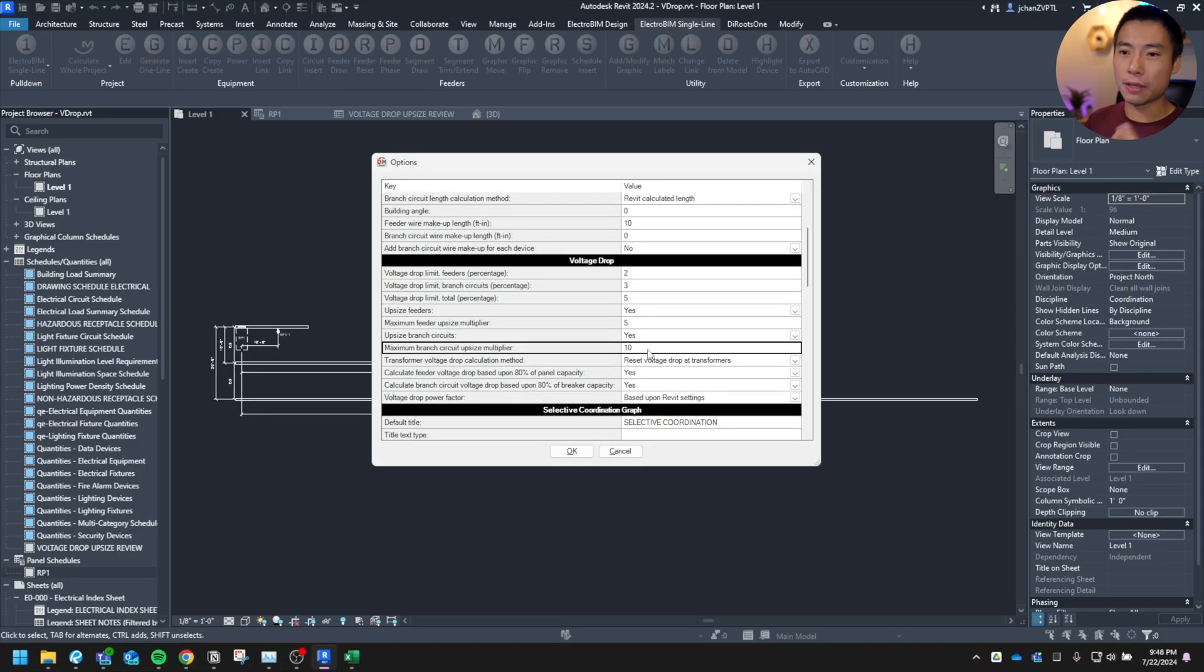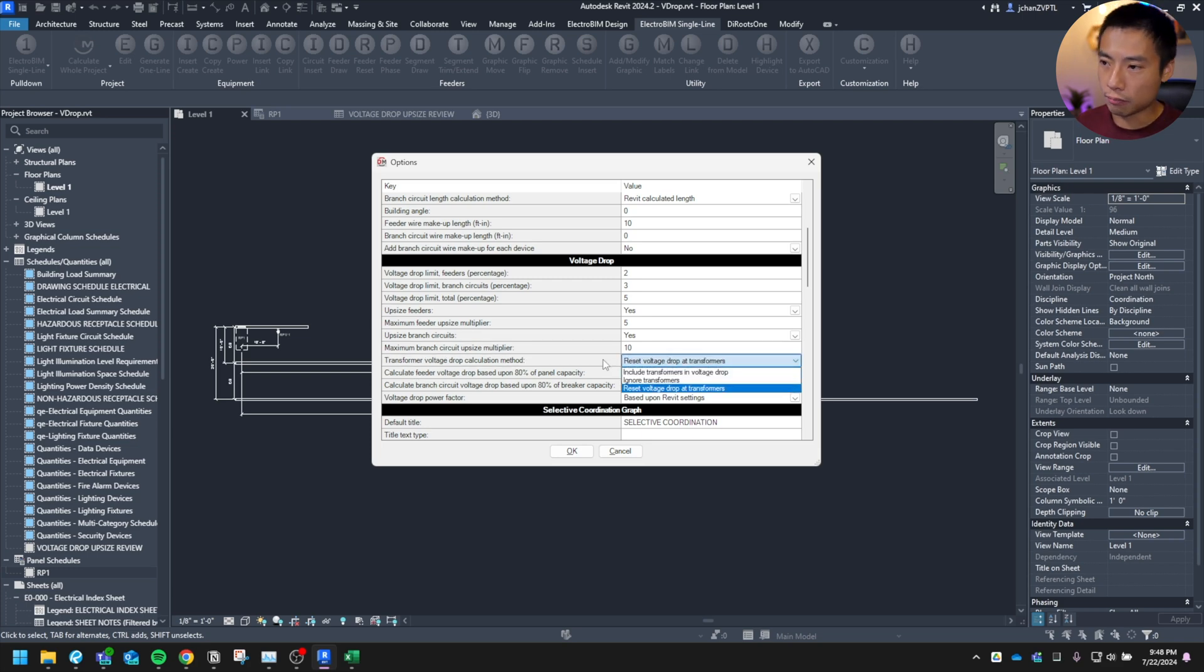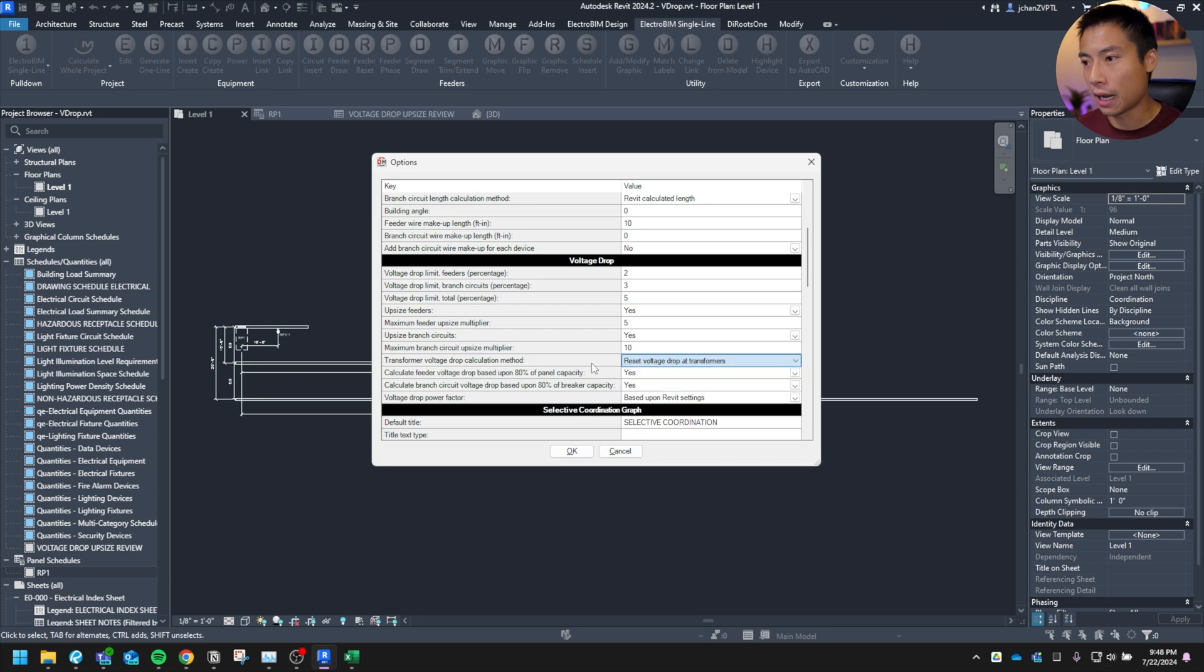What this will do is that it'll limit the amount that'll be upsized because after a certain amount of upsizing, there's something wrong with the design. Like you shouldn't be running a one-aught for a receptacle circuit at all. Like you're coming from the wrong panel. So if you limit this, what's cool is that I'll show you in a second voltage drop schedule will exceed that in the percentage. And then you'll see like something's beyond 3%, you have a problem. And then that'll bring it to your attention to fix that design. That should be coming from a different panel. It shouldn't be coming from this one going 500 feet that way. All right. So that's what that parameter does. You can reset at transformers cause you can adjust the taps to get your voltage back.